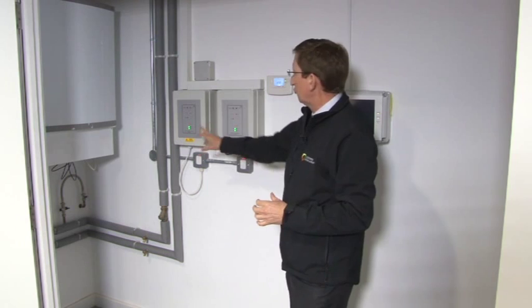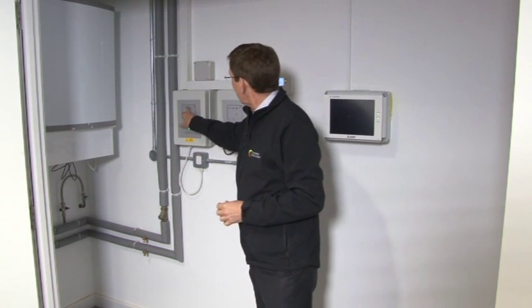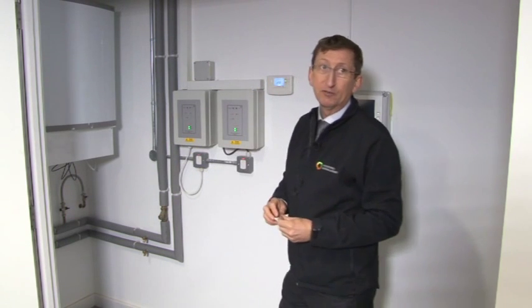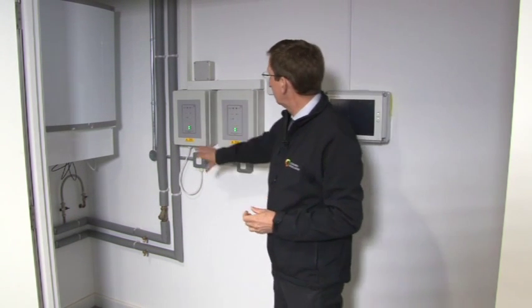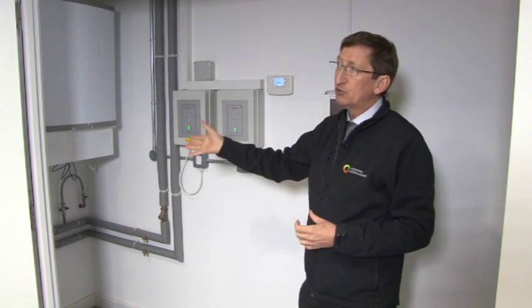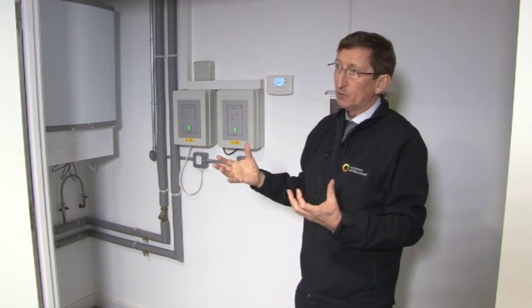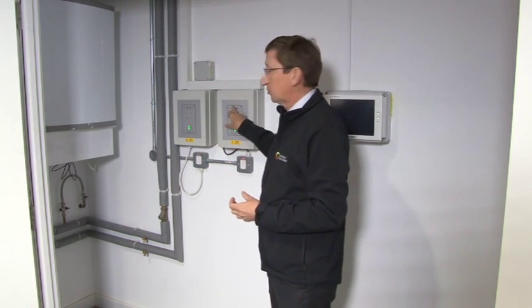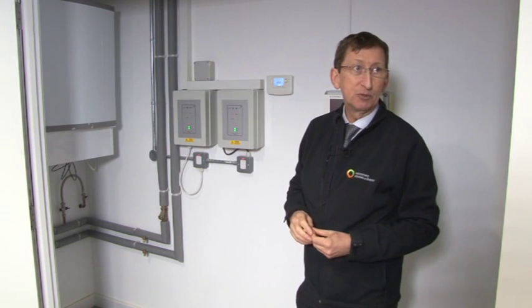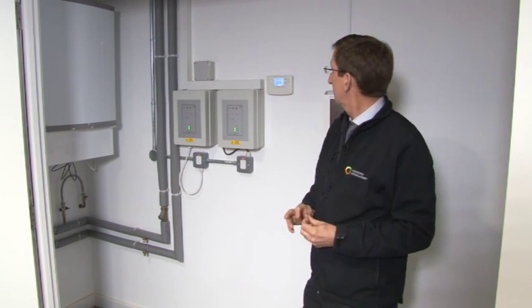And that's what these two control panels here are doing, controlling those heaters. Okay, so there's a preset temperature on the controllers, which you'd set up to the required temperature. The ventilation units are looking at the return air temperature coming back to them, which you want to be, say, 20 degrees C. You set the dial here to 20 degrees C, and it'll control to that temperature, bringing the heating batteries on as and when they're needed to maintain that temperature.